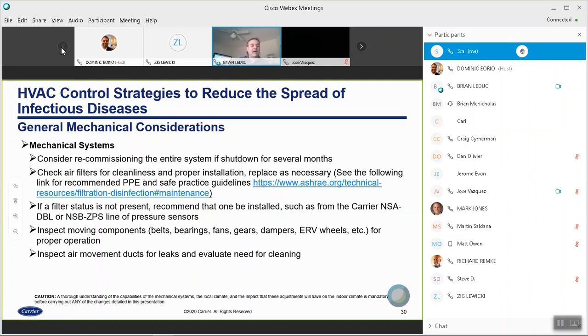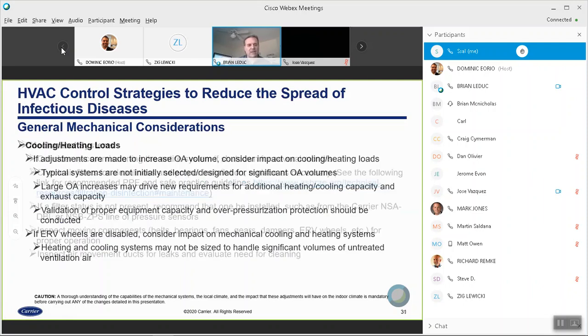You have a line of sensors. You know, inspect the moving components, belts, bearings, fans, etc. Inspect all your air ducts for leaks. Do they need to be cleaned? So again, just good, solid mechanical guidance when you're bringing a unit back online after a prolonged shutdown.